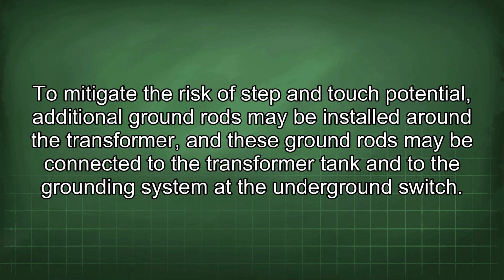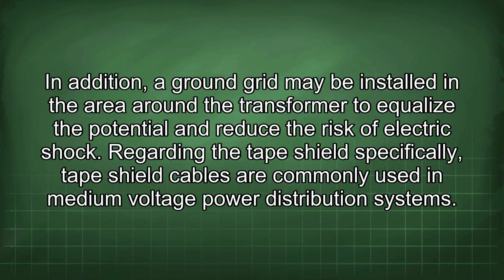To mitigate the risk of step and touch potential, additional ground rods may be installed around the transformer, and these ground rods may be connected to the transformer tank and to the grounding system at the underground switch. In addition, a ground grid may be installed in the area around the transformer to equalize the potential and reduce the risk of electric shock.